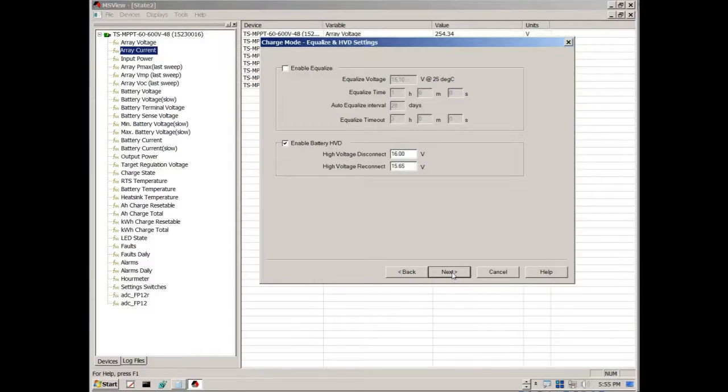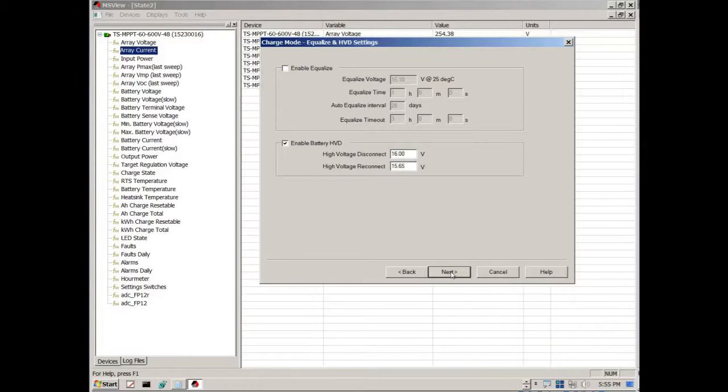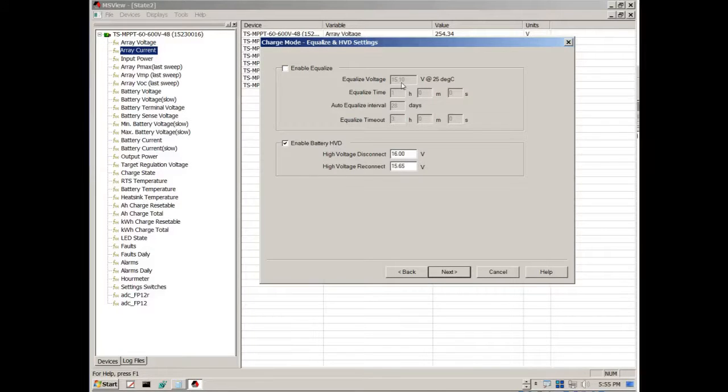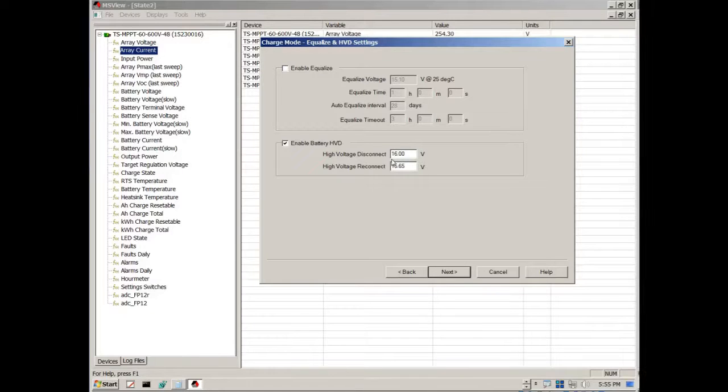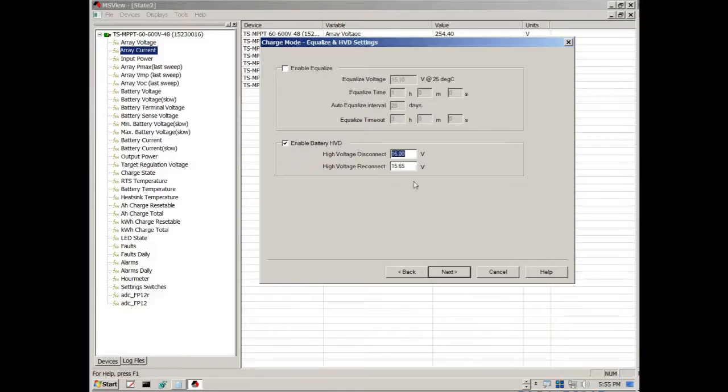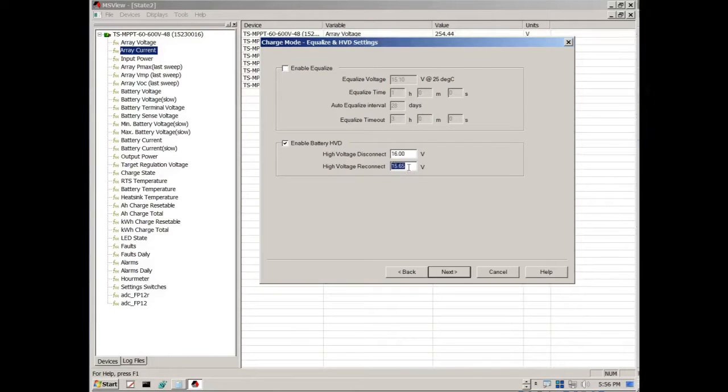And it's pretty much the same thing. If you want to equalize what the equalized voltage is, again a multiple of two, or a division of two. So for instance whatever this is, equalization would be 31.3. So you divide that by two and you get that voltage. And so the high voltage disconnect, I want it to disconnect at 32 volts. So you say 32 divided by two will give you 16. And reconnect at 15.65. So again 31.3 divided by two equals 15.65.